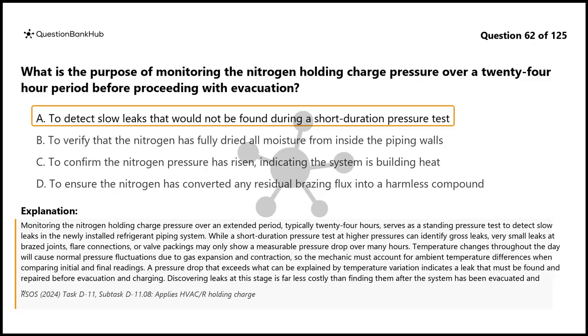Temperature changes throughout the day will cause normal pressure fluctuations due to gas expansion and contraction, so the mechanic must account for ambient temperature differences when comparing initial and final readings. A pressure drop that exceeds what can be explained by temperature variation indicates a leak that must be found and repaired before evacuation and charging. Discovering leaks at this stage is far less costly than finding them after the system has been evacuated and charged with refrigerant.